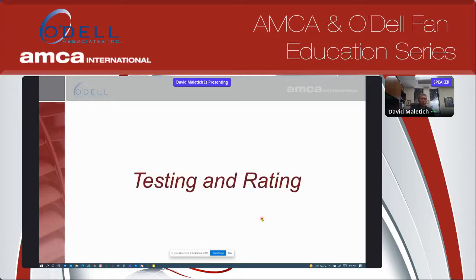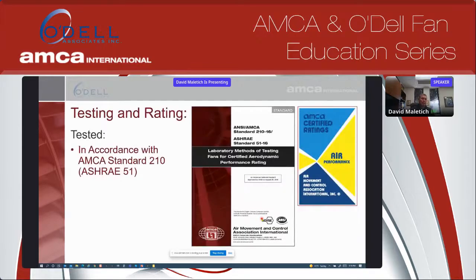All right, let's talk a little bit about testing and rating of fans. Fans are tested in accordance with AMCA Standard 210. AMCA, the Air Movement and Control Association, pretty much governs the methodology for testing and rating a fan. So when you're looking at how brand A and brand Z were tested, if they're AMCA certified products, you can be pretty much assured that the same testing methodology was used for both products.